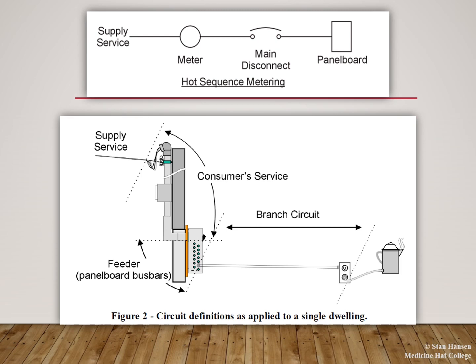Hot sequence metering means that we're going to come in from the supply line, we're going to go through the meter base, and then we're going to go to our service box after that. This means that that meter base is always hot, and if the service utility company ever has to do work on it, they're going to be working on a hot device unless they disconnect it from the transformer, which again is going to be another hot device.